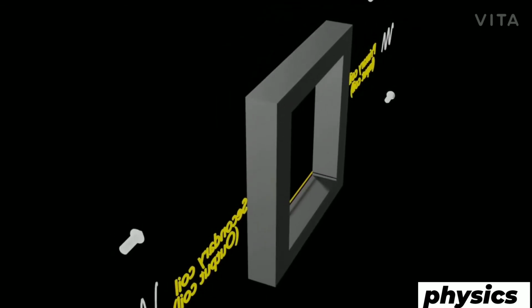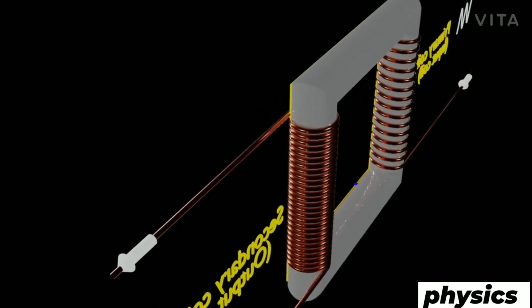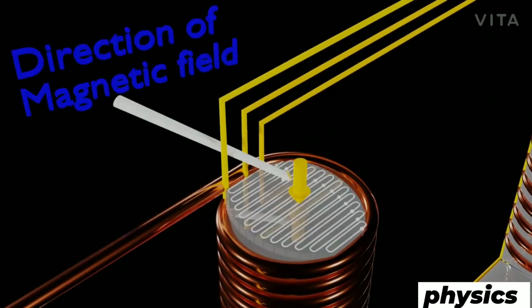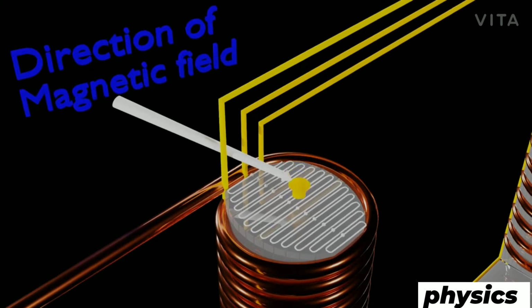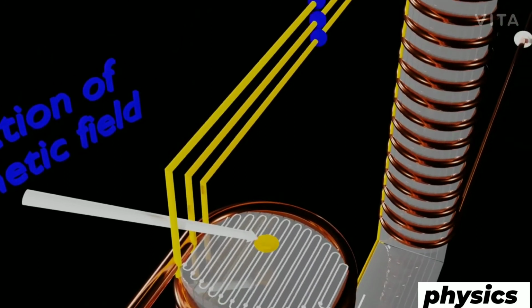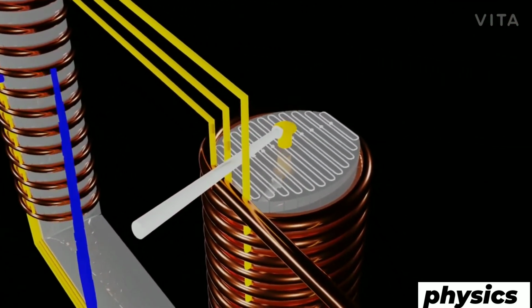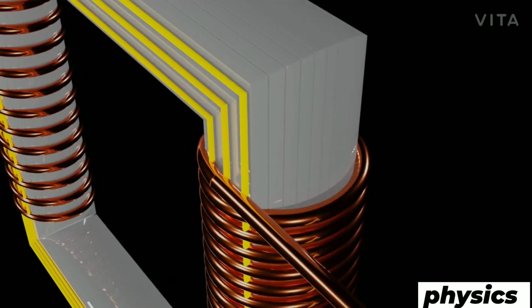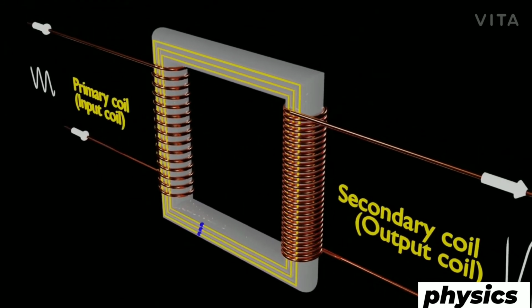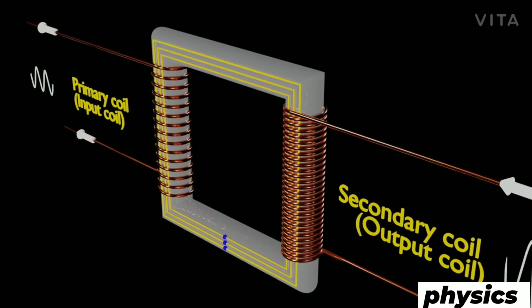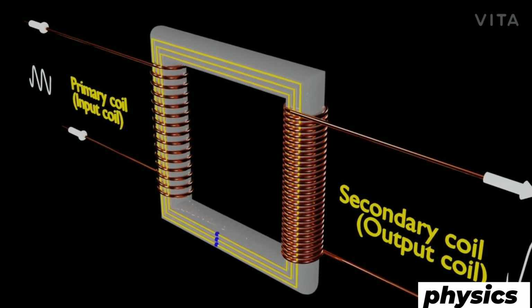On the other hand, if we use thin insulated metal sheets stacked in layers, the layers of insulation serve as a barrier to eddy currents. So eddy currents can only flow in narrow loops within the thickness of each single lamination. Since the current in an eddy current loop is proportional to the area of the loop, this prevents most of the current from flowing, reducing eddy currents to a very small level. Thus there is a lesser power loss in the form of heat loss.